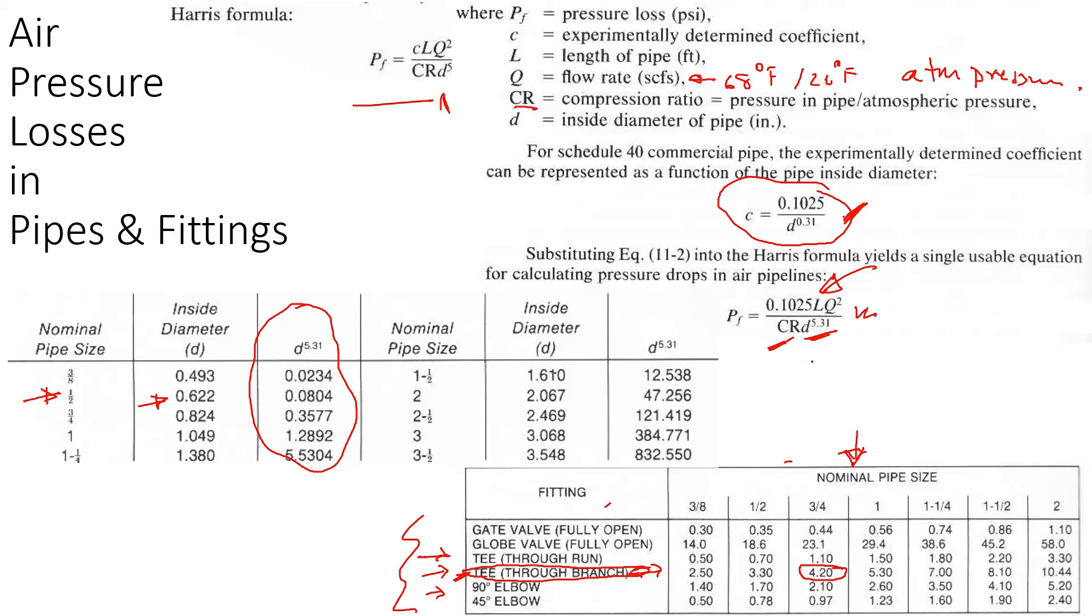The compression ratio is the pressure divided by the atmospheric pressure. In the English system you do psi absolute divided by 14.7 psi absolute atmospheric pressure. So let's say a compressor is running at 120 psi. That's 120 psi gauge plus 14.7 divided by 14.7, which gives the compression ratio.